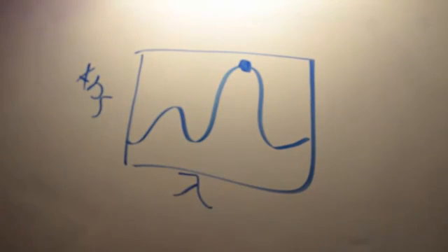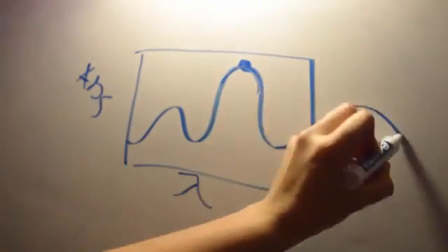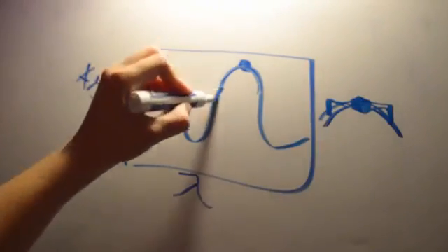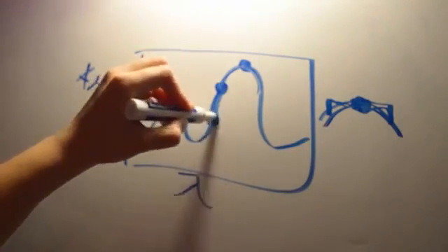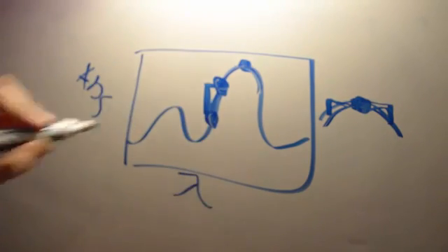Second, the curve is relatively flat, so there's going to be little variance if the monochromator drifts or the width of the transmitted band changes. Because if you look at this when you zoom in, the graph is quite flat, so if there's movement, there's not going to be much of a change. But if you choose somewhere here and there's a movement, this is a greater change in the absorbance.